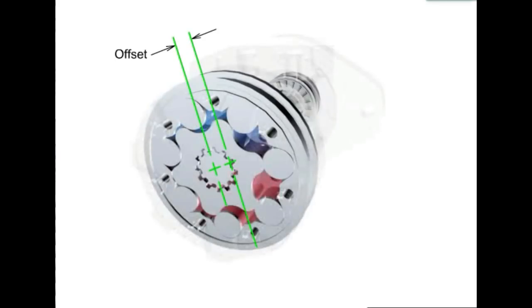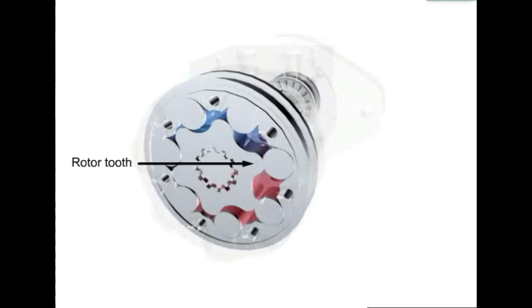The rotor sits offset in the cavity of the stator. An open cavity between the rotor and the stator is created by the offset of the rotor, which has one less tooth than the stator. One tooth of the rotor is always opposed to one roller tooth of the stator. The cavity is divided into two pressure zones by the opposing teeth. One side of the opposing teeth is high pressure, and the other side is low pressure.